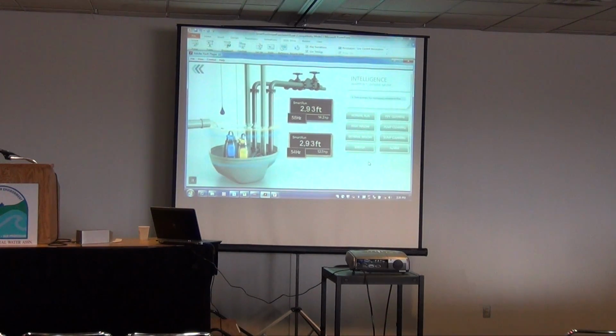But when we look at this, with each controller operating independently of one another, we've got about an 8-inch area where every day, at your discretion, say at midnight, those units are going to randomize those starts. I compare it to flipping a coin. You've got about a 50-50 shot of it starting up. We're used to the lead pump starting, then we alternate, and the lag pump is then the lead pump on the next cycle. Well, erase that out of your mind, because now we start that pump independently, and it is possible for pump 1 to get more cycles in a day than pump 2.